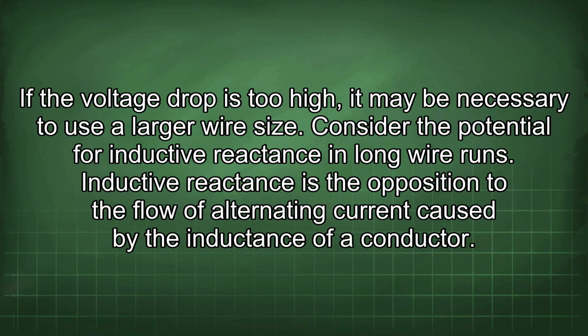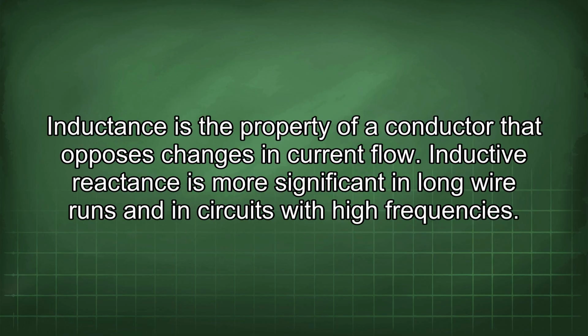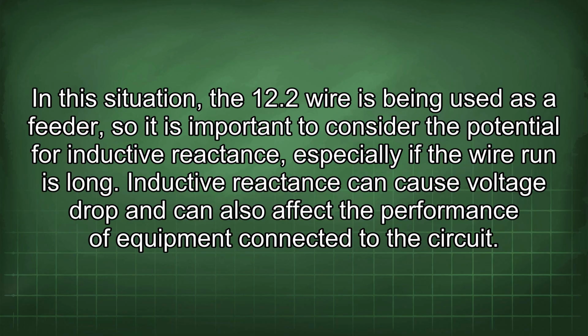Consider the potential for inductive reactance in long wire runs. Inductive reactance is the opposition to the flow of alternating current caused by the inductance of a conductor. Inductance is the property of a conductor that opposes changes in current flow. Inductive reactance is more significant in long wire runs and in circuits with high frequencies. In this situation, the 12.2 wire is being used as a feeder, so it is important to consider the potential for inductive reactance, especially if the wire run is long. Inductive reactance can cause voltage drop and can also affect the performance of equipment connected to the circuit.